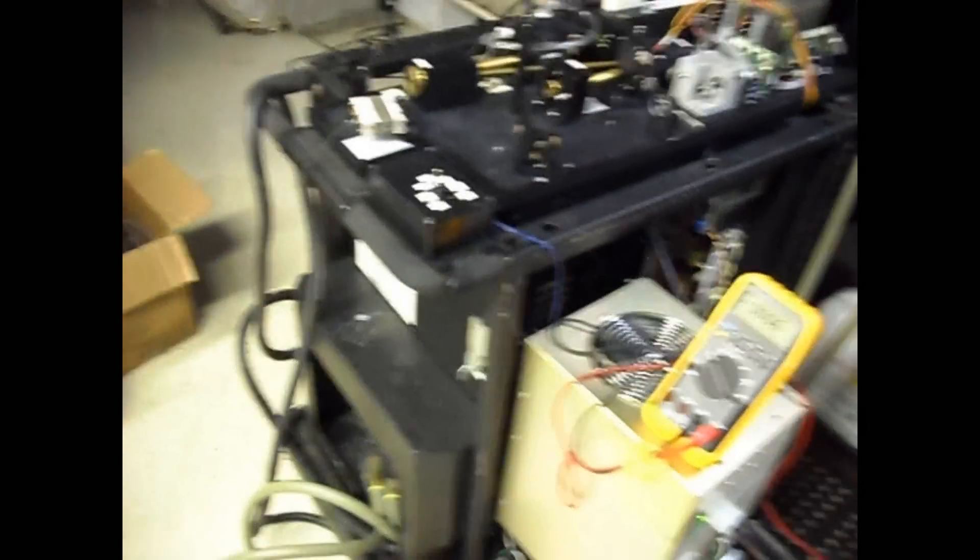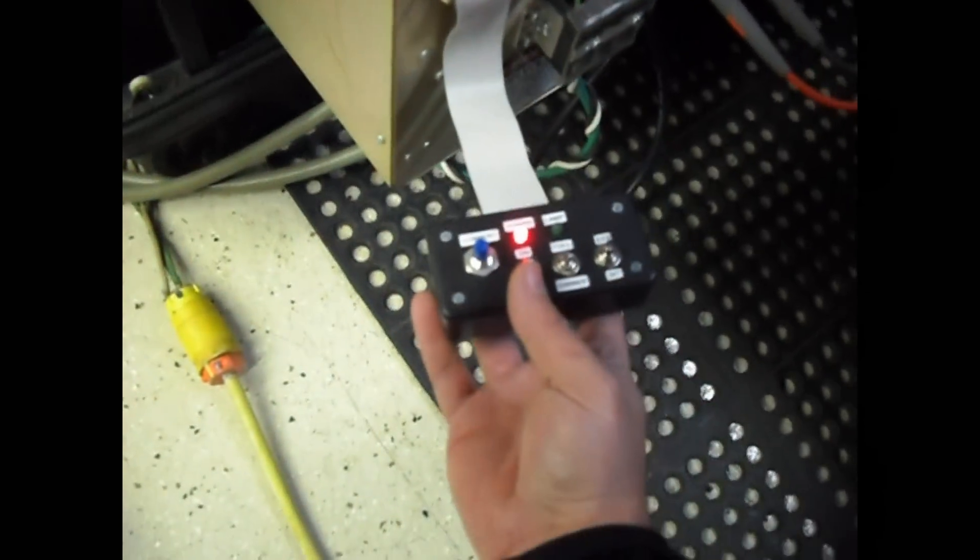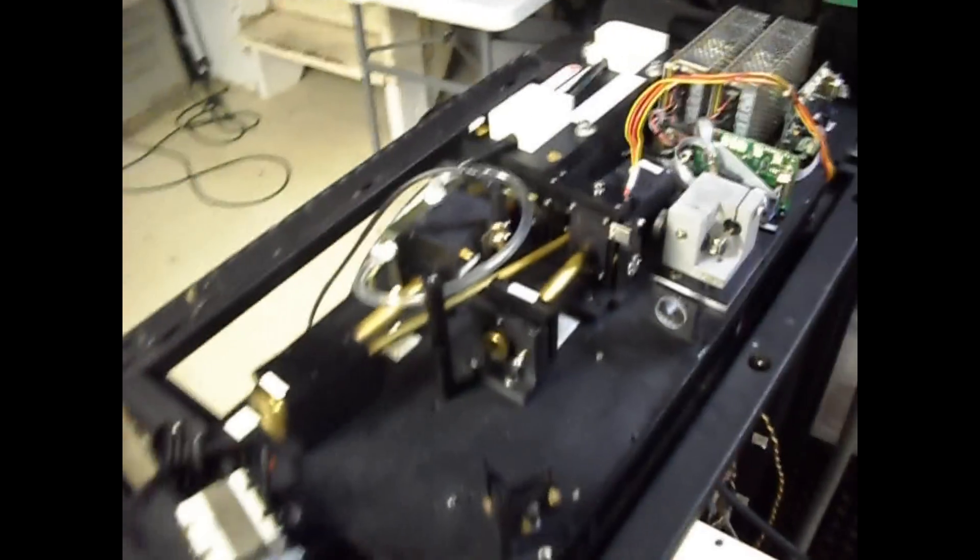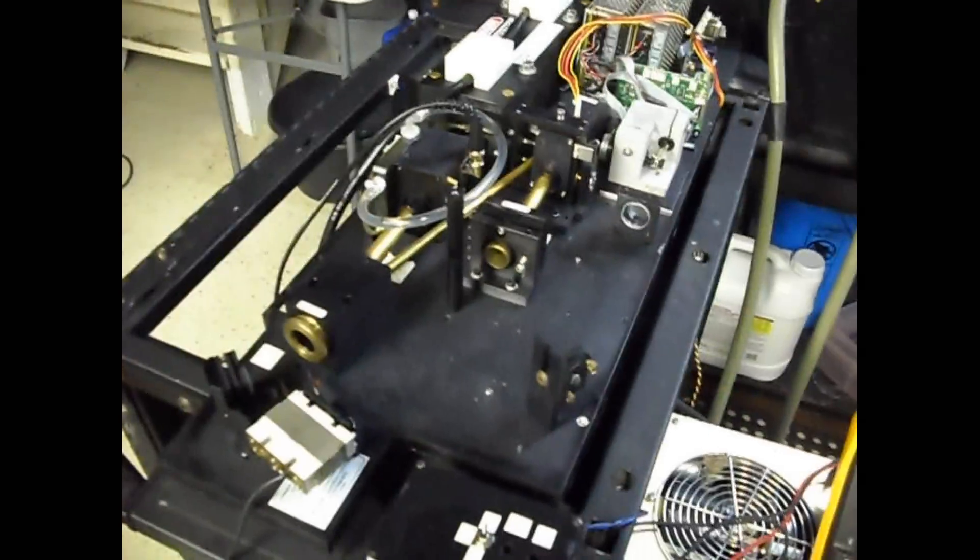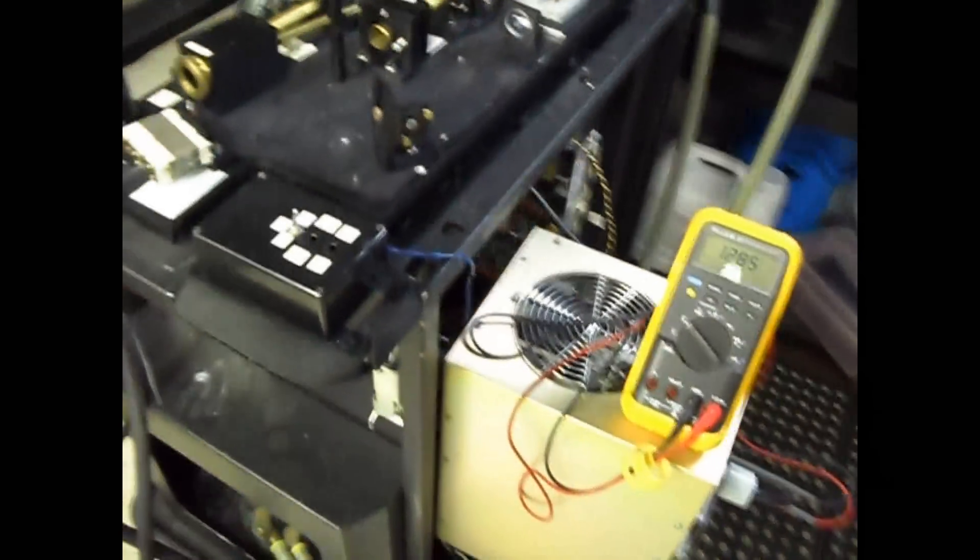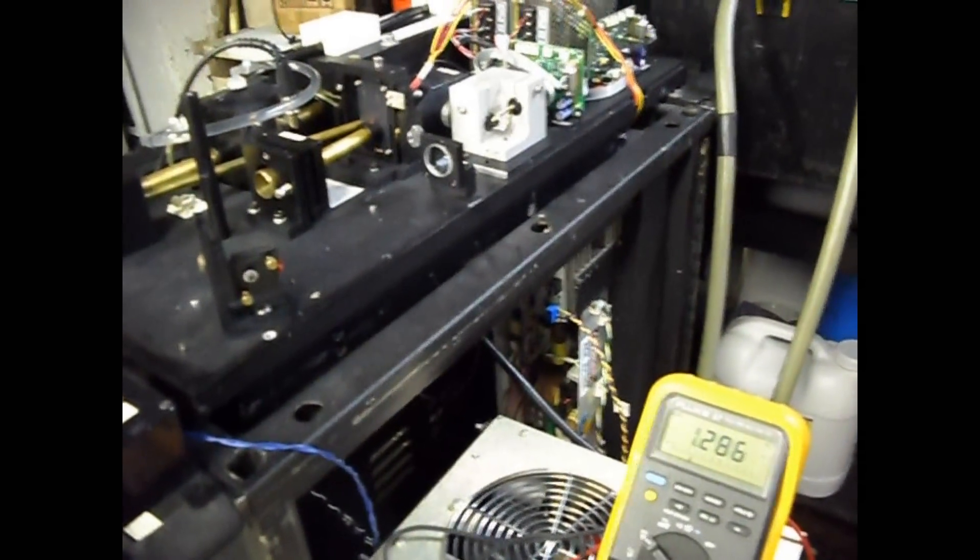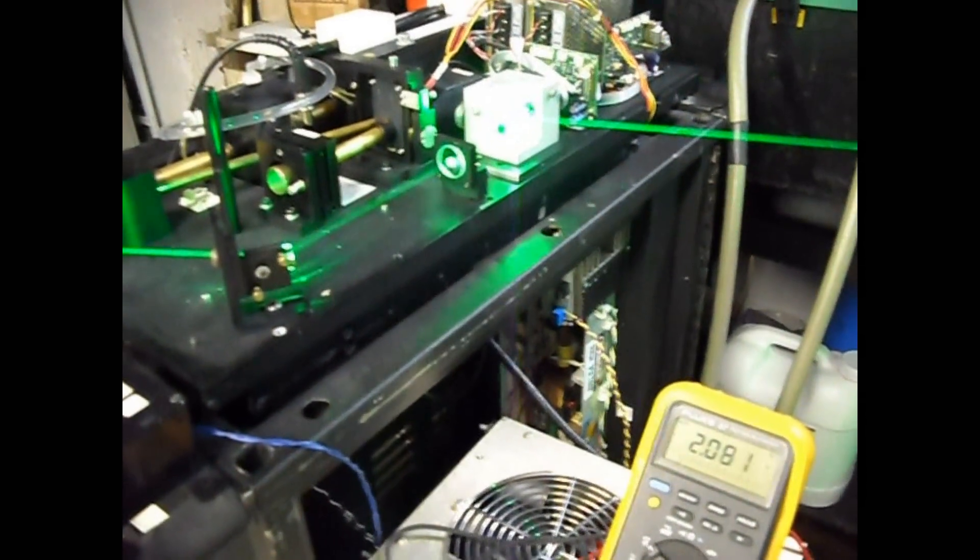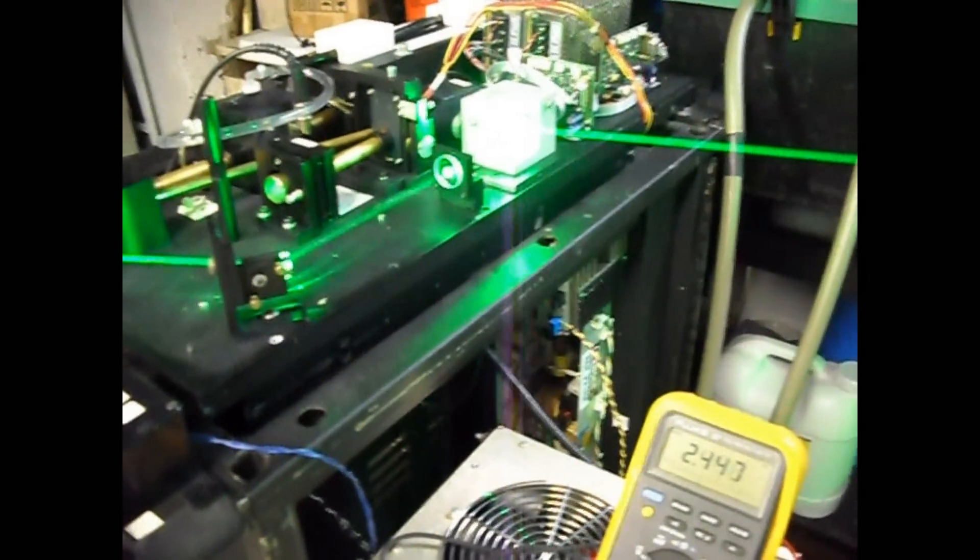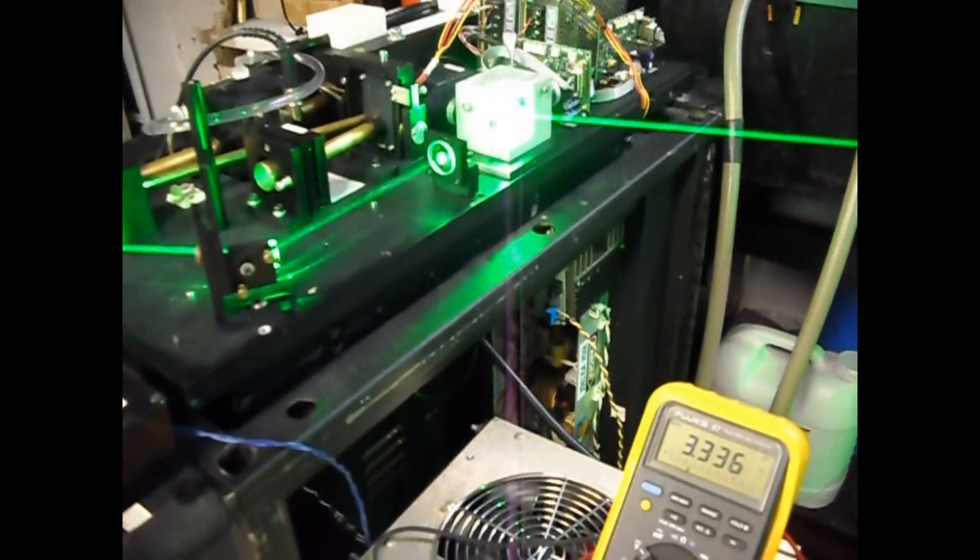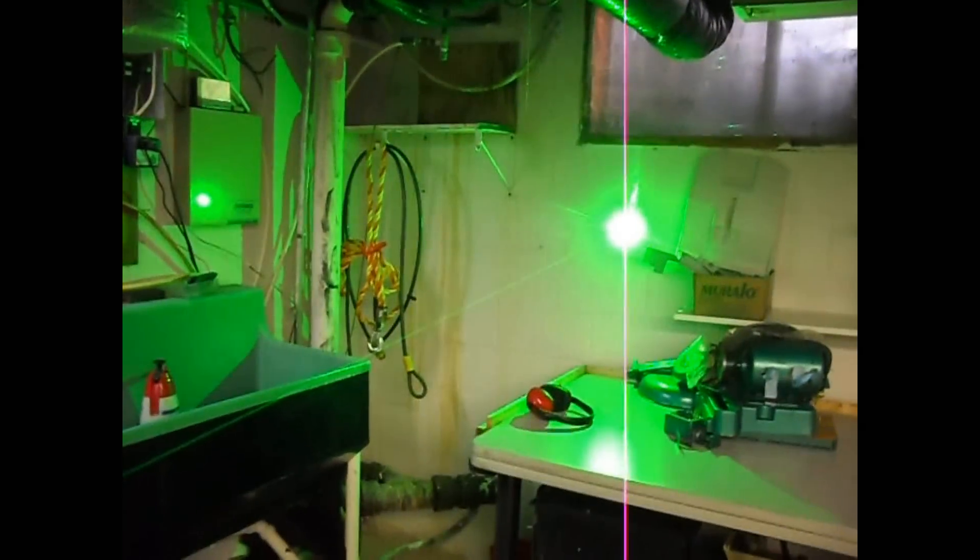So anyway, we'll go ahead and fire the lamp. Go down here, flip this switch. Okay, the lamp's now on and the lamp's getting 12 amps of current. Obviously no lazing yet because the lamp's just basically simmering. So from here we'll go ahead and crank the current up and then we'll start to see it laze. Let's see here, there we go, 21 amps, it's lazing. And we'll go ahead and crank this sucker up to about 33 amps. And as you can see, we got a nice very bright spectacular beam.